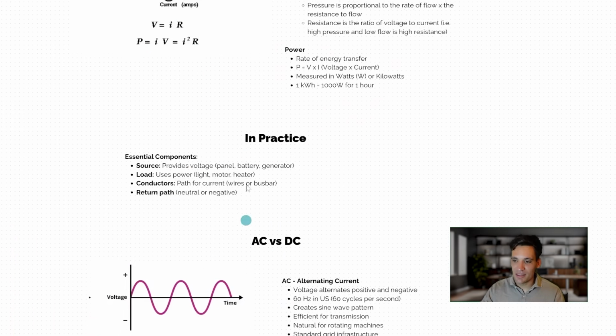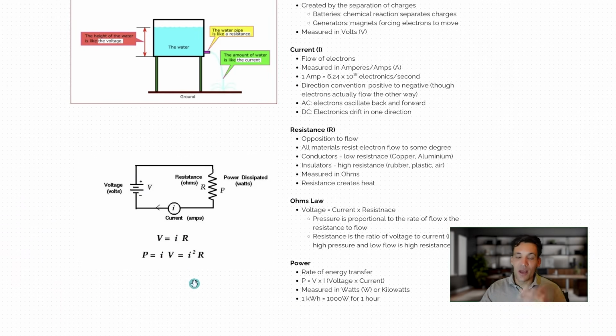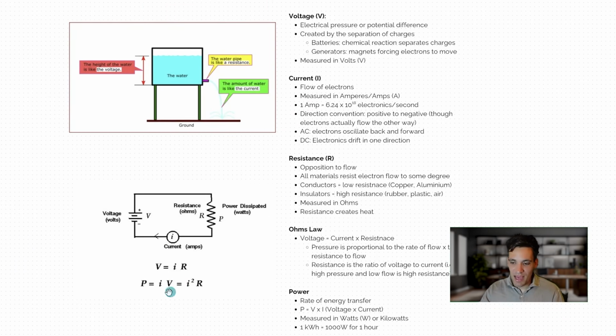The reason is that if you go back to our formula for power, our appliances use power at something like 200 volts or 240 volts, depending where you are. When you need to transmit a huge amount of power, the power you're transmitting is proportional to the voltage times the current. So if you have a low voltage, you need a high current to transmit a lot of power. But if we replace voltage with I times R, we can see that the power losses in the transmission line are proportional to the current squared times the resistance. Which means if you're transmitting power at a very high current, then even if the lines have a small resistance, you'll lose a huge amount of power in the transmission lines, basically making it not very efficient or effective at all.